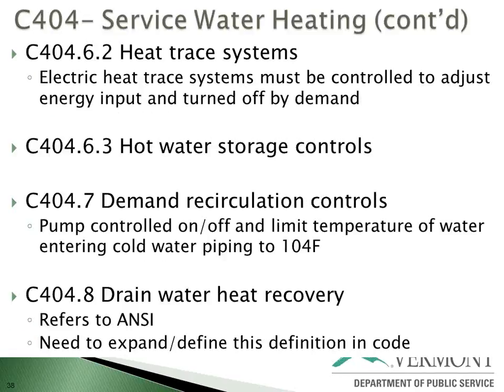Heat trace systems - I interpret that as the heat tape as well. Is that correct? Something I probably need to look more into, but I take that as the heat tape that's on service hot water piping to keep it at a certain temperature in the pipe. That also has to respond to demand and be controlled to adjust the energy input going into that system, and that reduces electric demand.